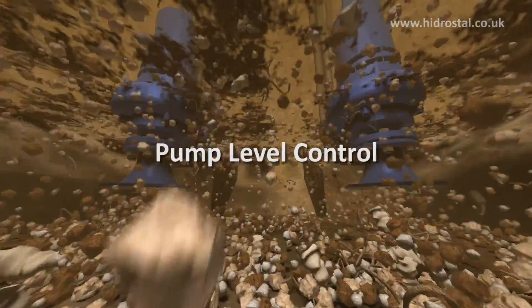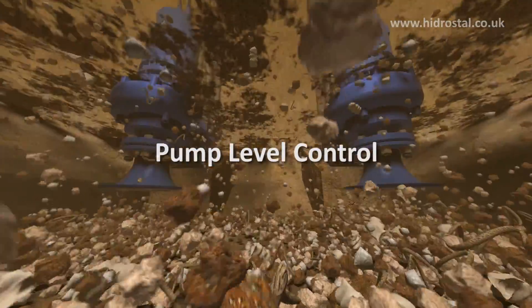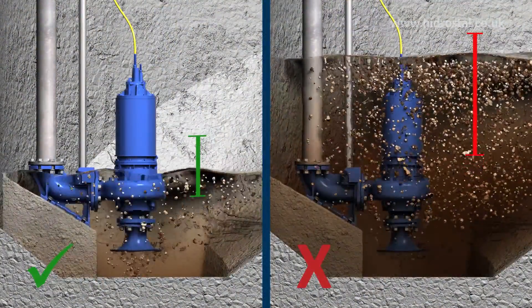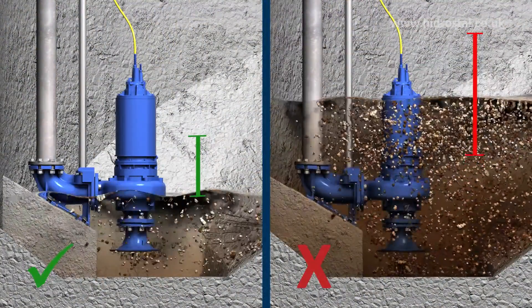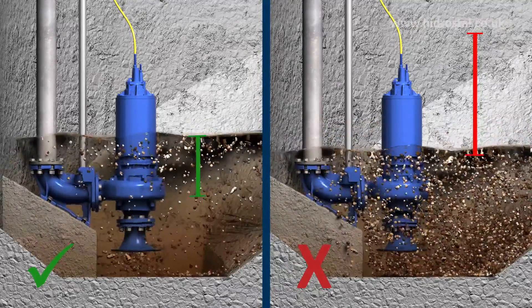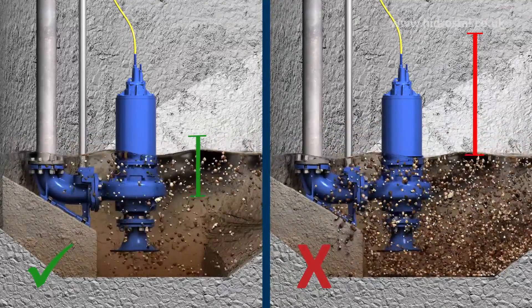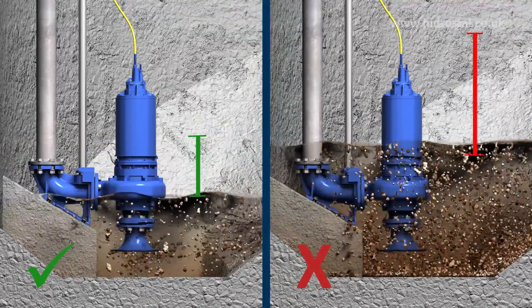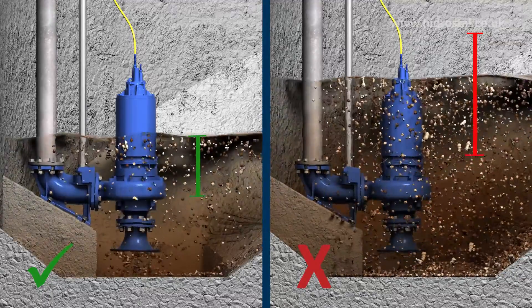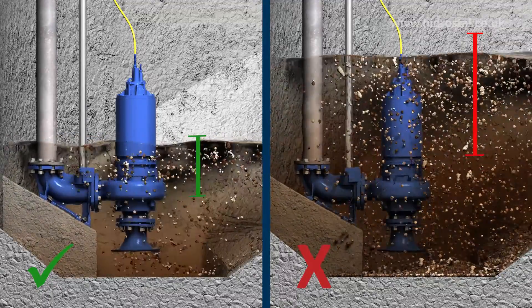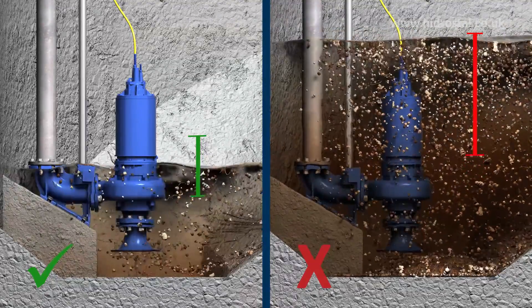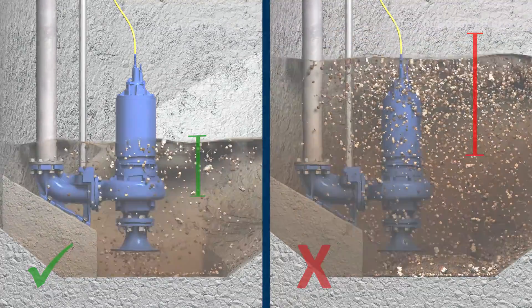Pump level control also plays a key role. The longer or more frequently the pump operates at a low level, the cleaner the wet well becomes. Cleaner wet wells mean less pump blockages and higher efficiency. Using immersible motors also means that the pump's drawdown cycle can be maximised without risk of overheating.